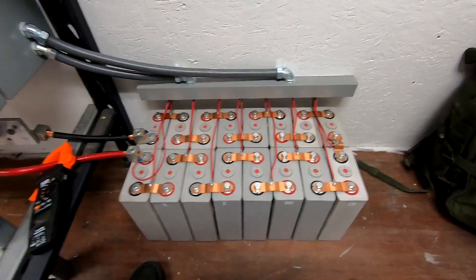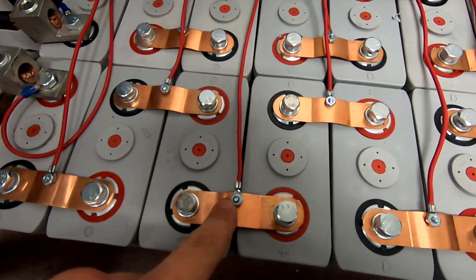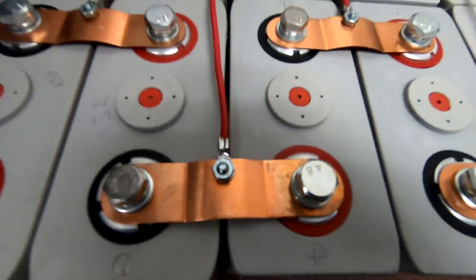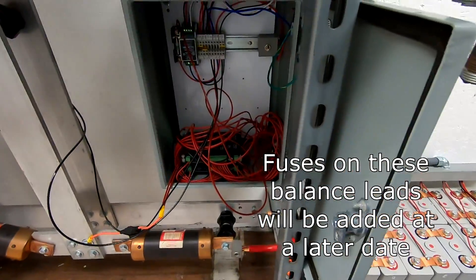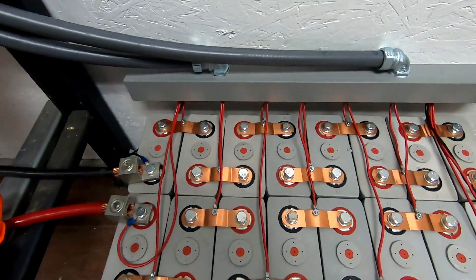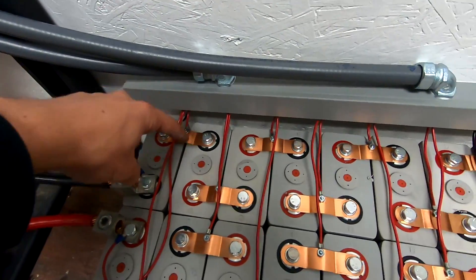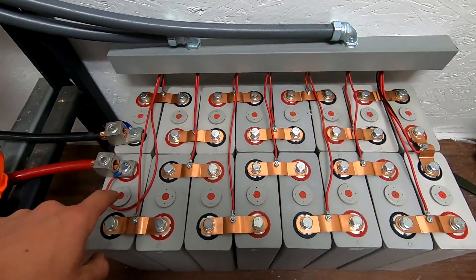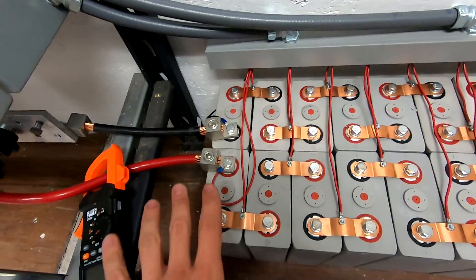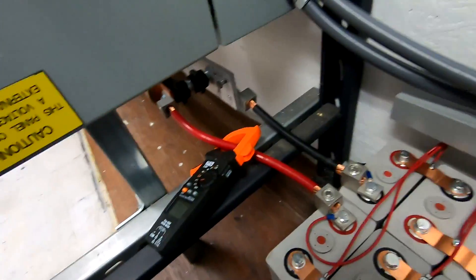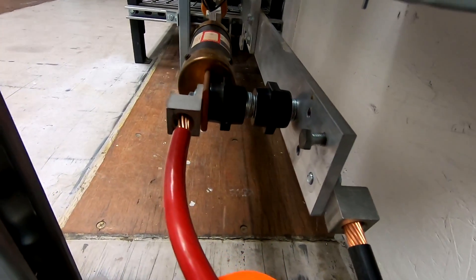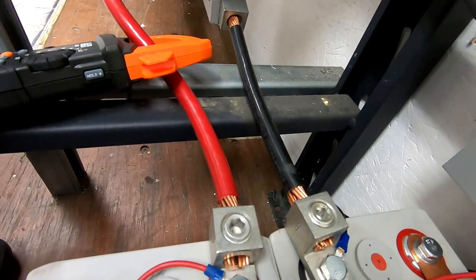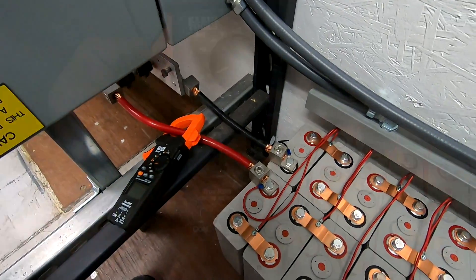So I've actually moved ahead quite a bit. I got all the balance leads in. I have these little ring terminals on here and the tiny 6-32 bolts and nuts. All these balance leads go back through into the balancers in the control cabinet with the wires all equal length. The way this is set up, here's our battery negative. And we swing around through here, snaking back and forth through all the cells and then come back down through. And that's how we were able to pull off right here, positive and negative at the center, just like I had planned on. And the reason that's nice is, like I said in the other clips, I'm right here at my bus bars, ready with a short piece of wire connected on, ready to go, tied in with the rest of the system.